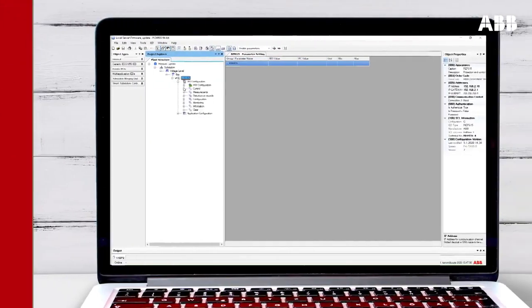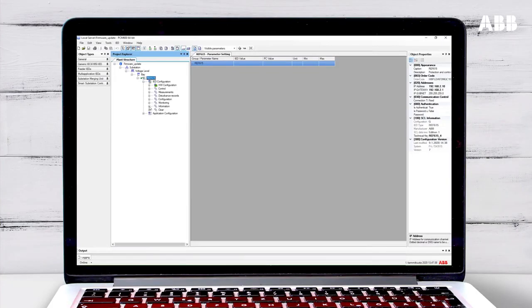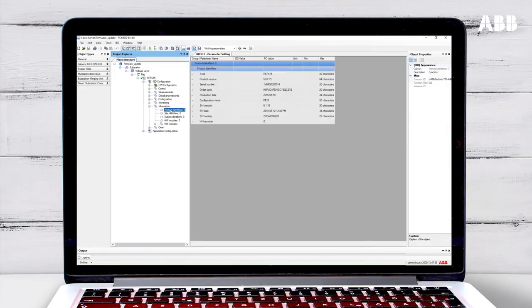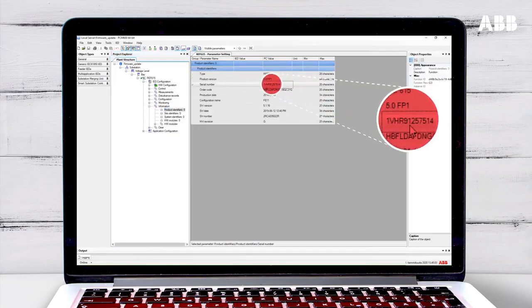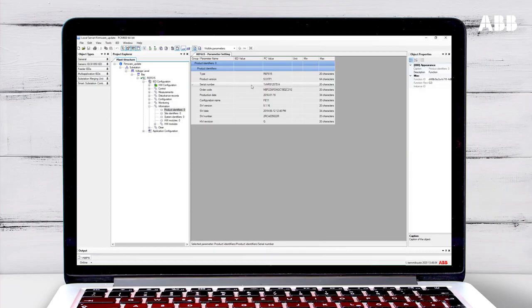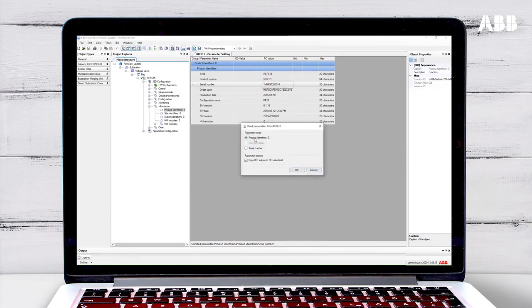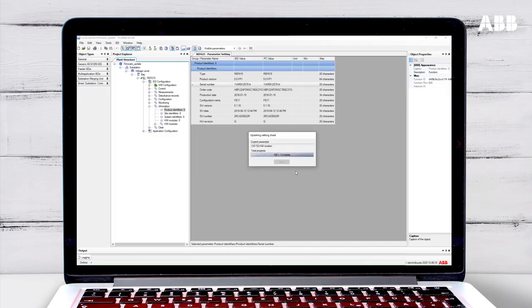You can also find the serial number in PCM600 if you have a live connection to the relay to read the parameters from the relay. Open IED Configuration, and then open Information. Right-click on the product identifiers and choose Parameter Setting to see the serial number of the relay. You will need to read the information from the IED to make sure that it is correct. Click on Read Parameters from IED, click OK, and then select to read the product identifiers. Click OK to import the data.